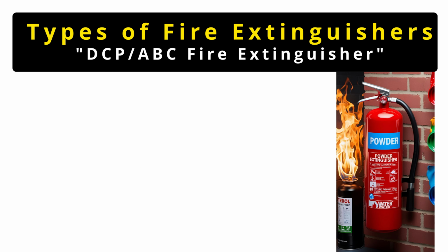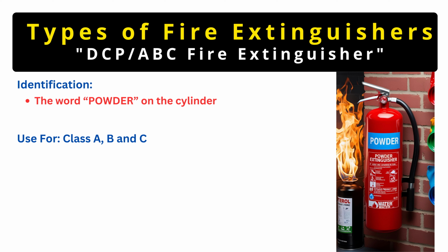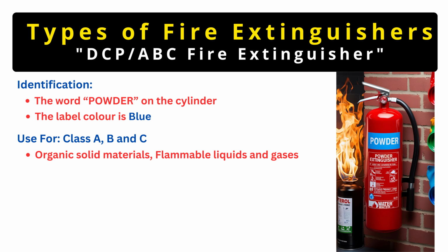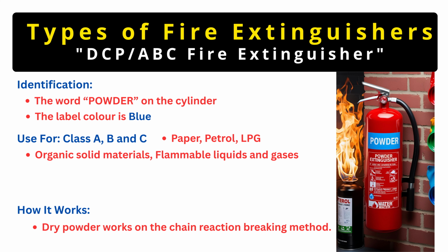Now we come to the dry powder fire extinguisher, also known as ABC extinguishers. Standard dry powder extinguishers are called ABC extinguishers because they are designed to tackle Class A fires, Class B fires and Class C fires. Dry powder extinguishers can be identified by the word powder on the cylinder. The label color is blue. Dry powder extinguishers are used for organic solid materials like paper, wood, cardboard, flammable liquids like petrol, paint, diesel and flammable gases like LPG, acetylene, hydrogen. This makes dry powder one of the most versatile extinguishers. Dry powder works on the chain reaction breaking method. It interrupts the chemical reactions at the molecular level and stops the fire instantly.